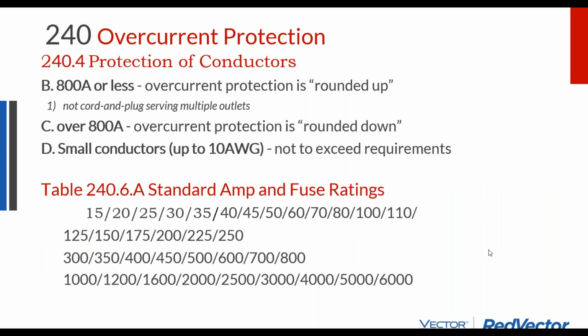So when you get to breaker sizing, the main thing is you calculate your overcurrent. So you have 16 amps of load on a circuit, and you add 25%, and that's 20. That's 19.8 amps. And you say, well, what do I do? If your calculations are 800 amps or less, then you take your load and your conductor sizing, and then you round up to the nearest breaker. So if I have a 16 amp load and that comes out to be 19 amps with my overcurrent calculation, I put it on a 20 amp breaker.